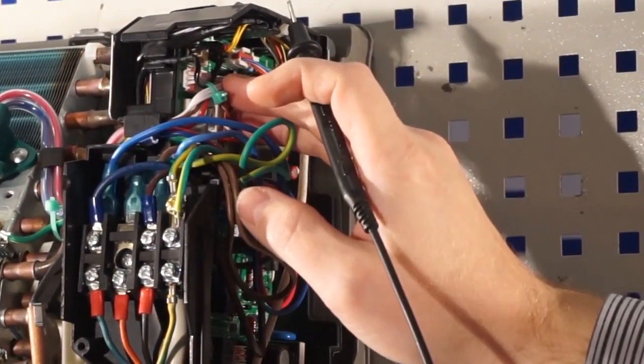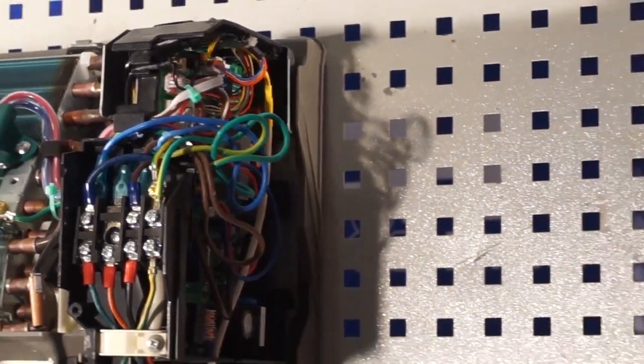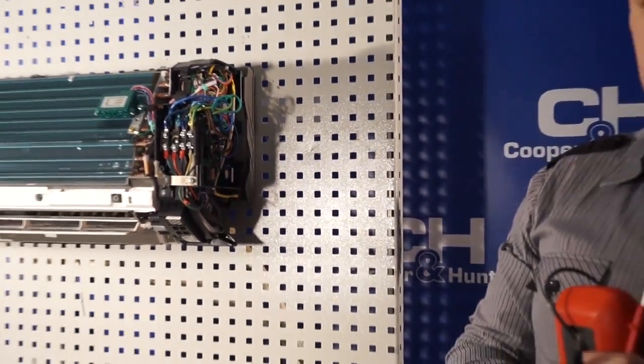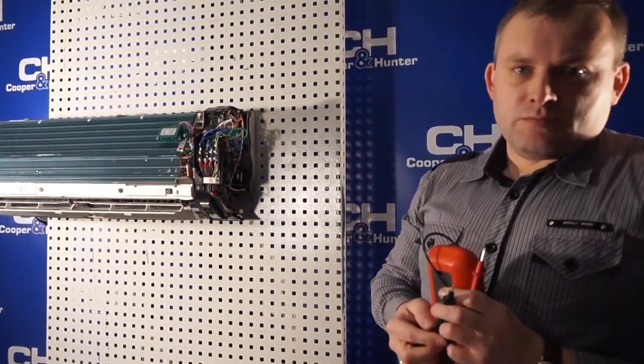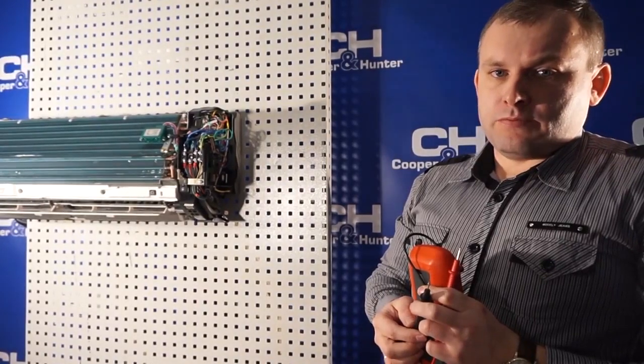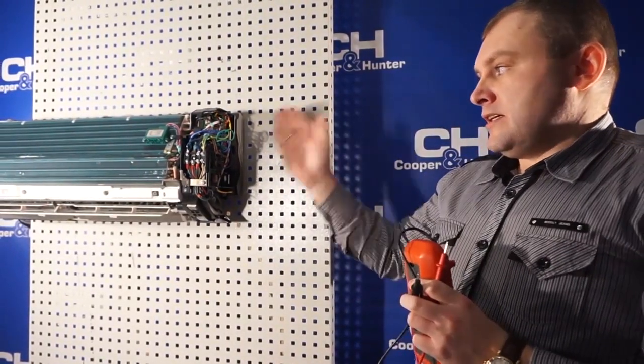The connectors are connected. For further operation, we need to replace the fan motor. If after that the error H6 does not disappear, it is necessary to replace the main board of the indoor unit.